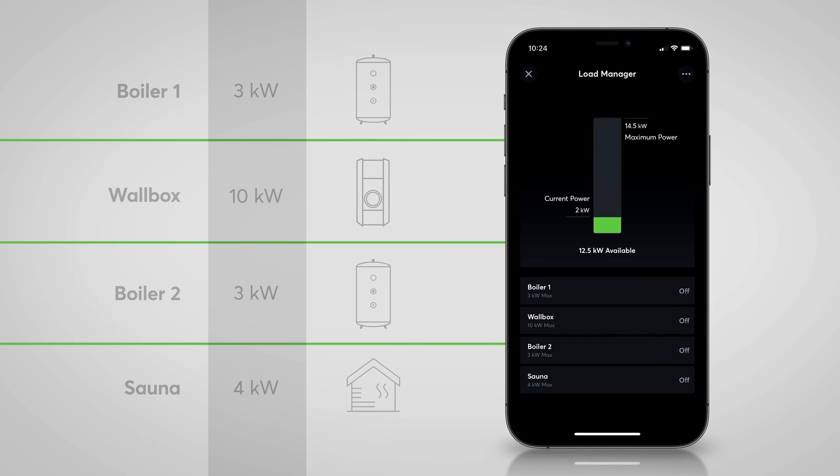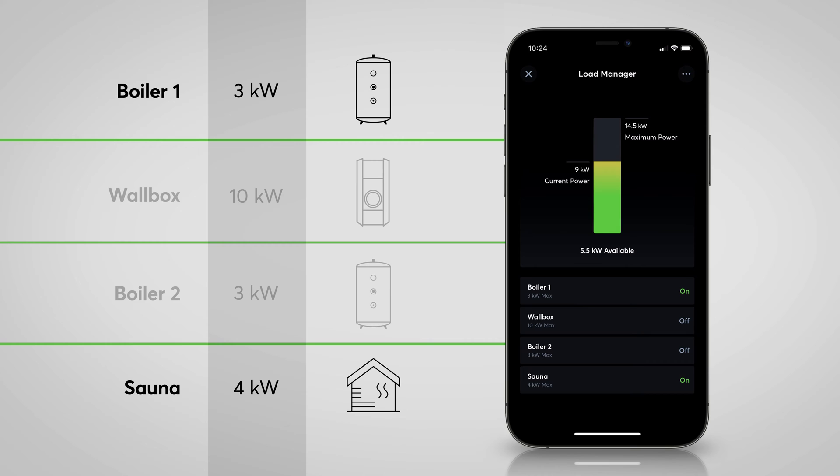This is where you can make use of the specifically developed new load manager function block in version 12.1 of Loxone Config. The load manager monitors the current load in a building and protects against overload. When the predefined maximum power limit is exceeded, the loads assigned to the function block are disconnected and locked according to a set priority. The devices can be controlled directly via the mini server or via one of our various supported interfaces.